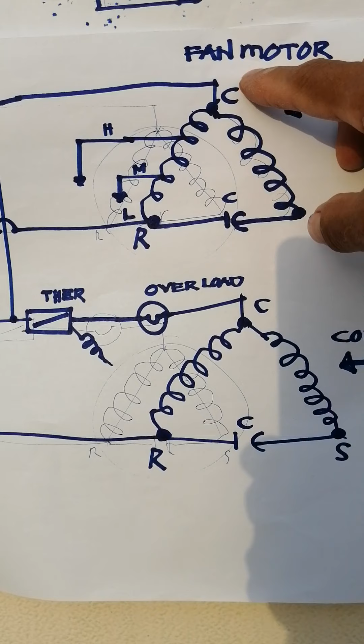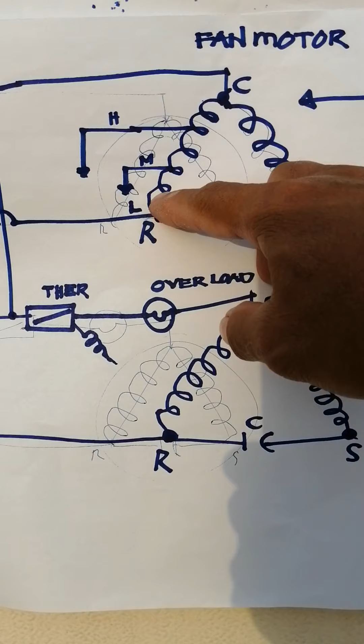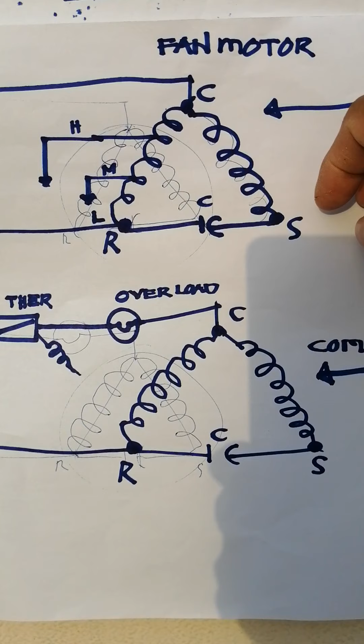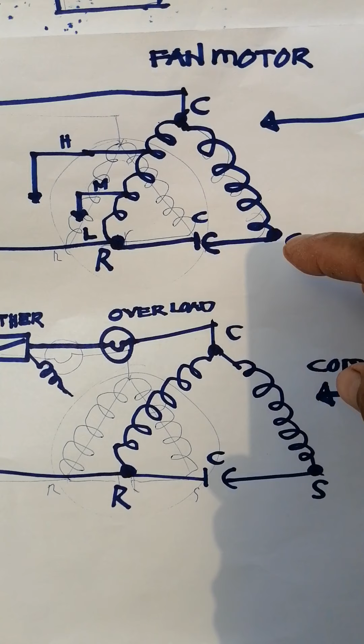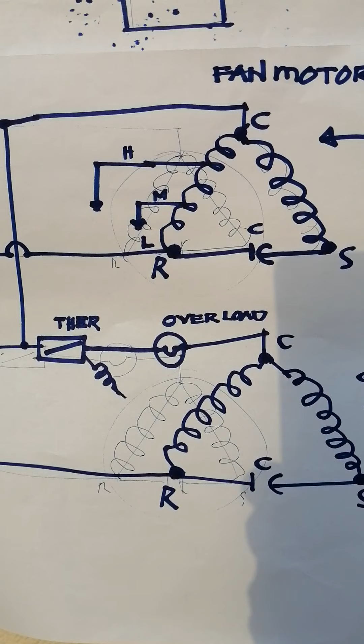That is one reason that the compressor will not run. How about if the compressor runs and the motor will not run? What is the possible cause? So the possible cause, we will go directly to the motor. Maybe this capacitor is defective, or this coil is open. Same as in the compressor, and maybe the motor itself is stuck. That's why it is not running. That is some possible cause.